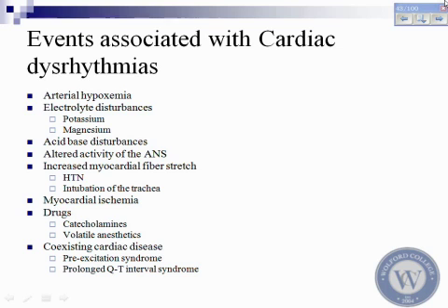So when you look at your screen, you look at your pulse oximetry, you look at the FiO2 that you're delivering to a patient. They had 3 deaths in Japan about 7 years ago, in the same operating room in the same morning, and they noticed that all the patients got tachycardic right before they went into asystole, and they couldn't figure out what was going on. Unfortunately, they were cutting corners, and they decided that they weren't going to have FiO2 monitors on the patients. The FiO2 is what actually measures the oxygen concentration that's leaving the anesthesia machine.